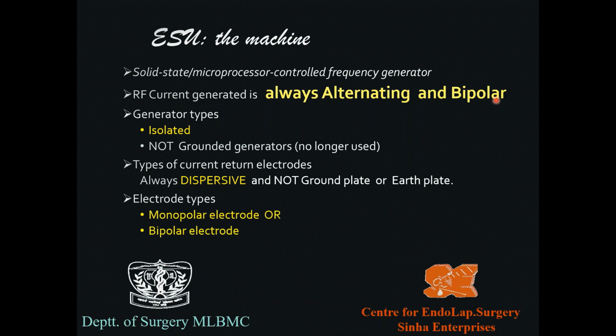And when we talk about the generator that we normally use, this electrosurgical unit, the generator is the electrosurgical generator, the machine that is there inside your OT. When using this electrosurgical unit, it can be isolated; in fact, it should be isolated. Initially, they were grounded generators. I'll tell you what a ground generator means. As for the types of current return electrodes, it can be a dispersive electrode, that is, how the current is coming back to your surgical unit.